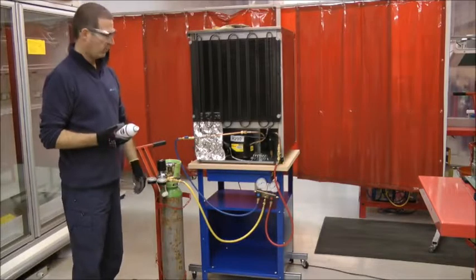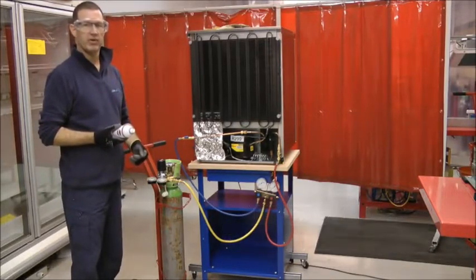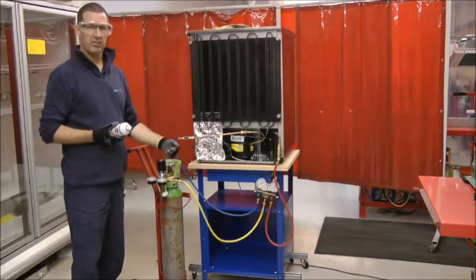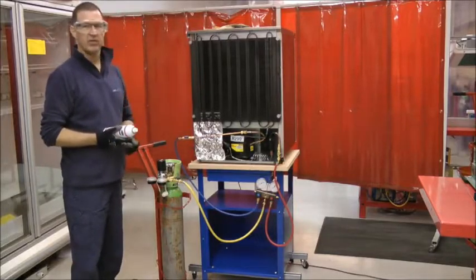Prior to evacuation, we want to carry out a low pressure test on the system using oxygen-free nitrogen. We'll take it up to a nominal 5 bar in the system and then we'll use soapy water to test our brazed connection.